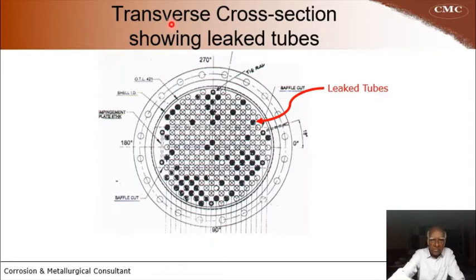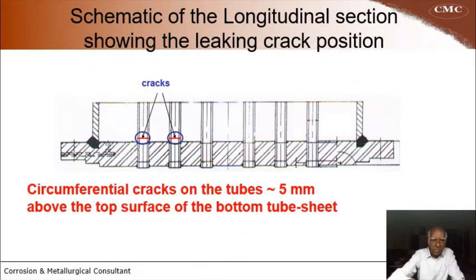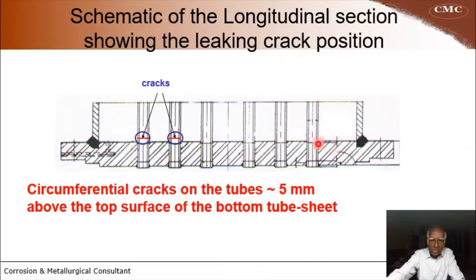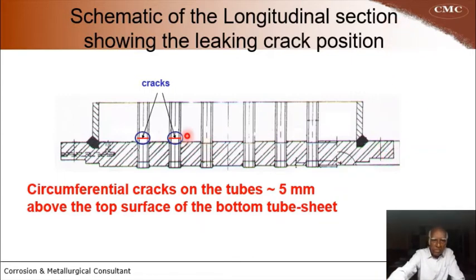This is the transverse cross section showing the leaked tubes. Approximately about 30% of the tubes leaked. This shows schematically the longitudinal section showing the leaking crack position. The cracks occurred just about 5 mm above the top surface of the bottom tube sheet. There is a similar tube sheet on the top also, and this indicates there is some problem in this area.